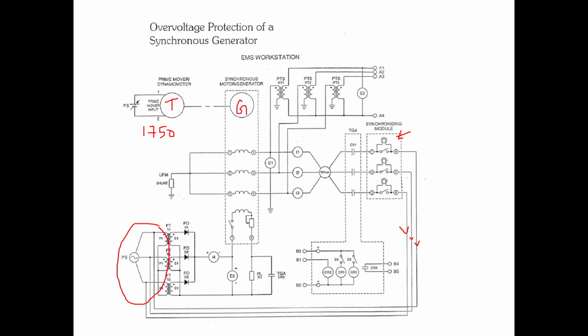When the lamps are dim, we close these contacts, and this CR1 is manually closed. We close this switch manually, so CR1 contacts are closed. Before synchronizing, we have to close the CR1 contact, and once the CR1 contact is closed and after synchronizing, the generator is now synchronized to the grid.